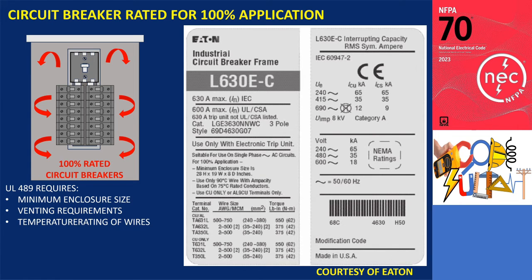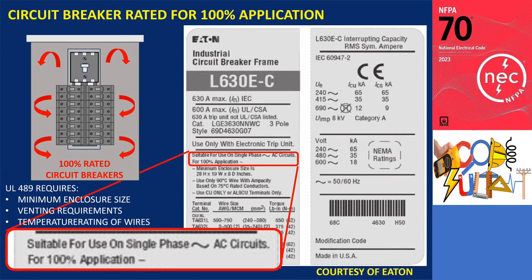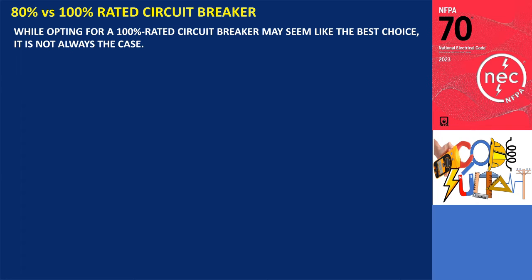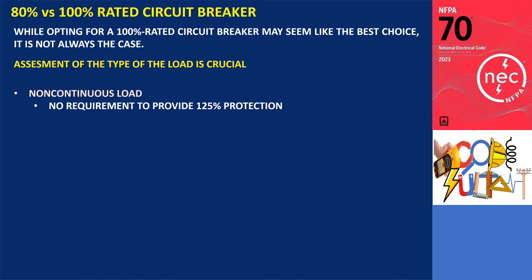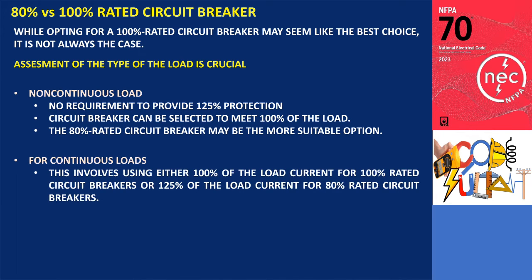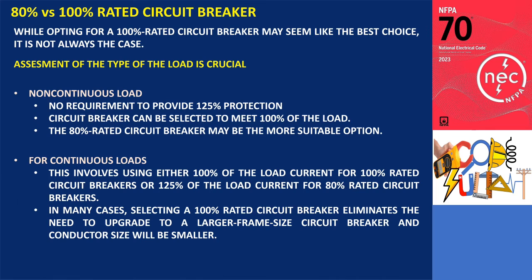It's important to note that a circuit breaker passing these additional tests is still not listed for continuous loading at 100% of its rating unless explicitly marked as such by the manufacturer. While opting for a 100% rated circuit breaker may seem like the best choice, it is not always the case. If the load is non-continuous, there is no requirement to provide 125% protection, and the circuit breaker can be selected to meet 100% of the load — in such situations, the 80% rated circuit breaker may be more suitable. For continuous loads, use either 100% of the load current for 100% rated circuit breakers, or 125% of the load current for 80% rated circuit breakers. In many cases, selecting a 100% rated circuit breaker eliminates the need to upgrade to a larger frame size, and conductor size will be smaller, making it the most cost-effective choice.